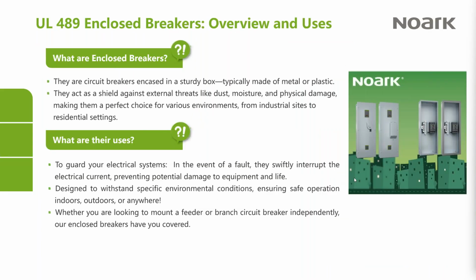Okay, so getting into today's topic, which is UL 489 enclosed breakers. So what is an enclosed breaker? As the name suggests, it's a circuit breaker that's enclosed inside a box. Enclosures in our industry are typically made of metal or more recently from plastic materials. And they're really there to both protect the equipment from things like dust and moisture and physical damage, but also to protect people from the live components that may be inside.